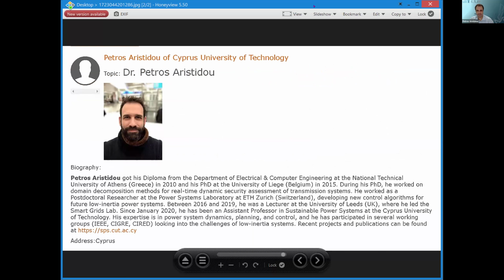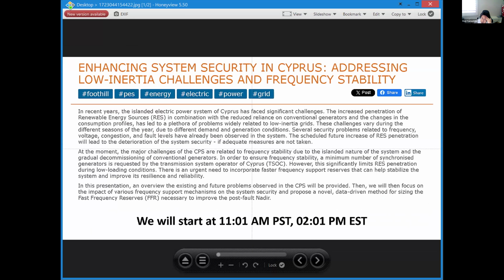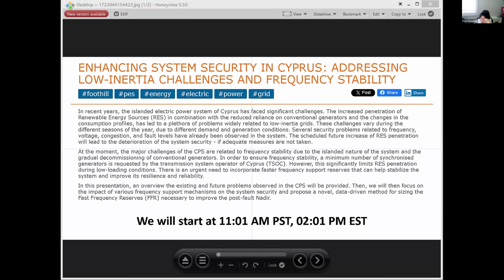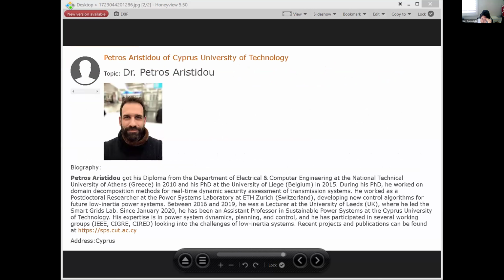Yeah. They usually select the constant impedance characteristics for active power, and that is the current selection. Although the actual load characteristic is not the pure constant impedance, they intentionally select it.